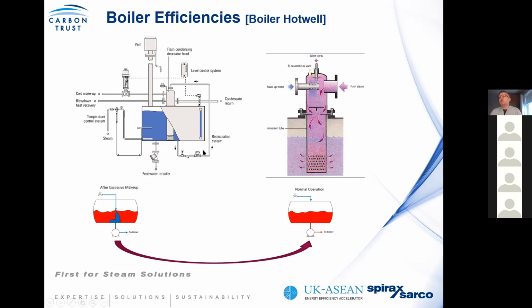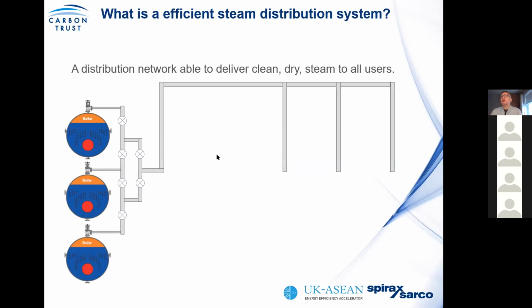And again, what we want to do is improve the quality of boiler feed water such that then you can reduce the demand for chemicals, reduce the demand for blowdown, and help create better quality steam, which is a higher quality steam, more efficient steam use, and a more efficient steam system. So let's consider now your distribution system. So what you're trying to do is generate high quality steam. And we spoke about the separation of steam from the boiler. However, your distribution system is quite large.